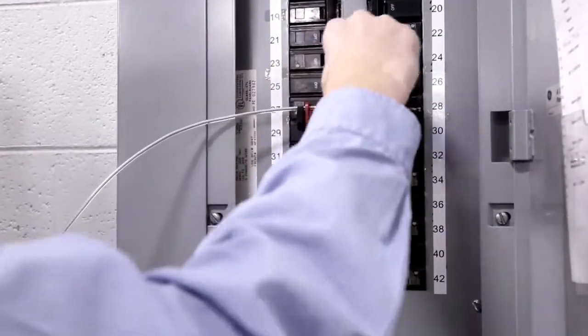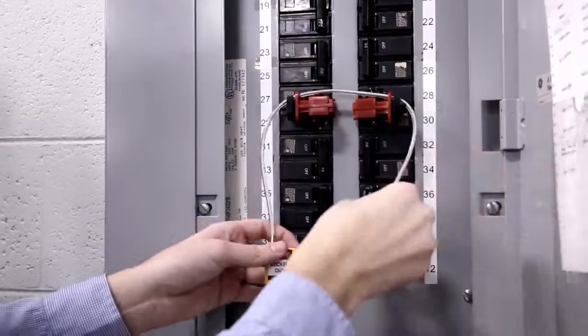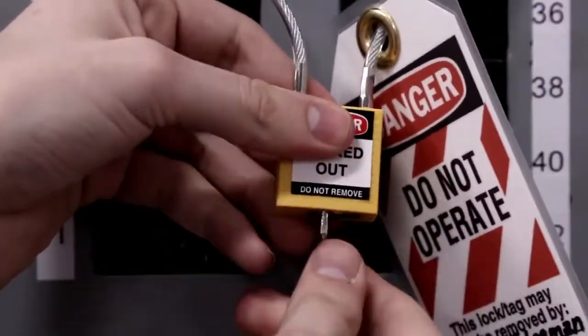Thread the padlock cable through all circuits to be locked out, place the worker's protective tag on the device, and lock the device.